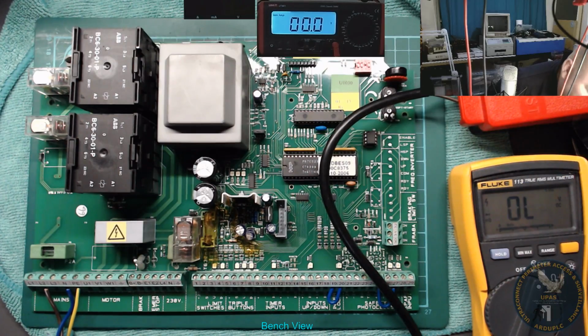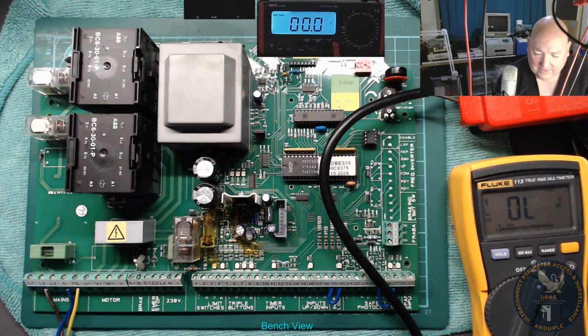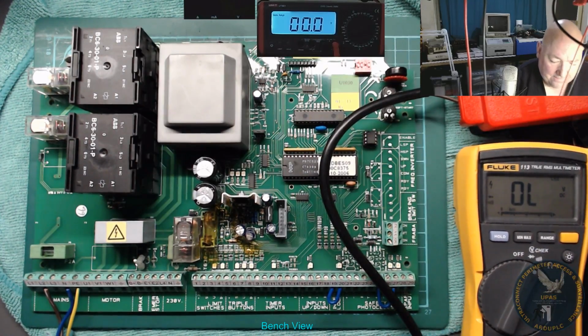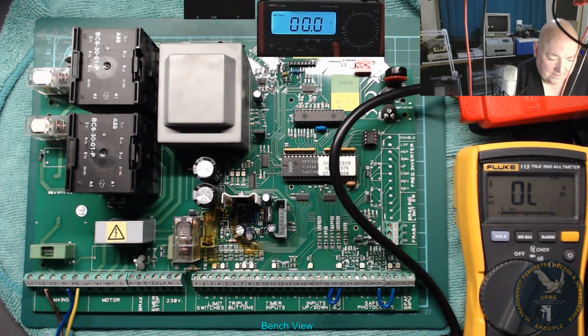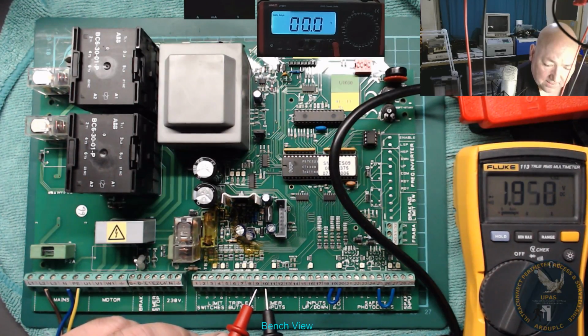We've got no stop circuits in, but we can do a few basic checks on voltage. Let's do the voltage check. We're on volts now, let's see if we've got 12 or 24 volts. 1.8 volts DC. Oh, hang on, what have we got?